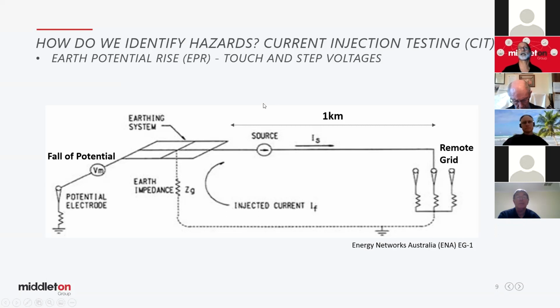We'll see a little bit more about that later, but quite easily, if this is our substation under test, we have a current source, an injection source, which we normally set off frequency, potentially 56 hertz or 58 hertz, because we only want to push around 5 or 10 amps around this circuit. And we don't want the fundamental, the imbalance that's returning through the ground, to interrupt or saturate our measurements. So we use an off frequency. And we like to inject this simulated fault across a transmission line. That's the best way to do it.